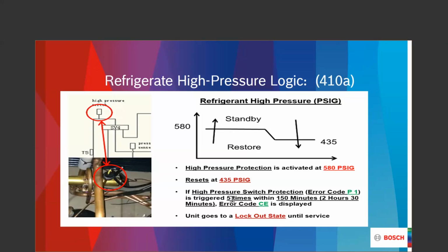So we're looking at dirty filters. We're looking at lack of airflow. We're looking at somebody's mismatched coil, someone who thought they could get by with a cheap install, and they put in a coil that was not conducive for a heat pump and made it an air conditioner, and it worked fairly well there. But all of a sudden we turned it into a heat pump, and it doesn't want to push that refrigerant into that little bitty coil, or that type of coil that's not conducive for all the refrigerant that's heading its way. So high pressure. Be very careful about the installs. Be very careful about what we're looking at, summertime, wintertime, because the condenser and the evaporator basically switch location.